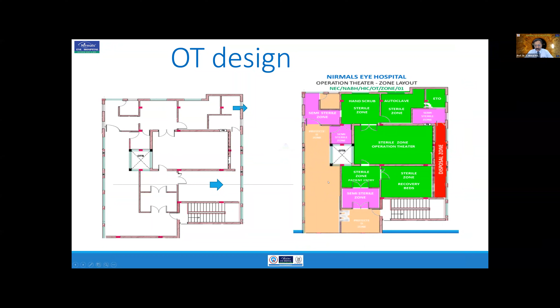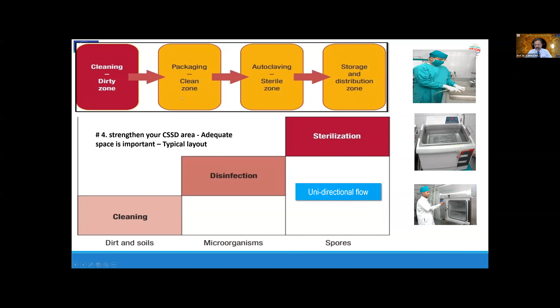You also need to understand that you need a proper workflow. Ideal is to have a unidirectional workflow with no mixing of dirty and clean products. This is the ideal way for a CSSD, or this is the important area. A good layout is important for cleaning, disinfection, and sterilization, and you also need good equipment for cleaning the equipments.